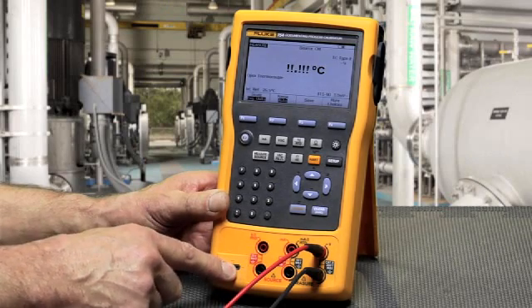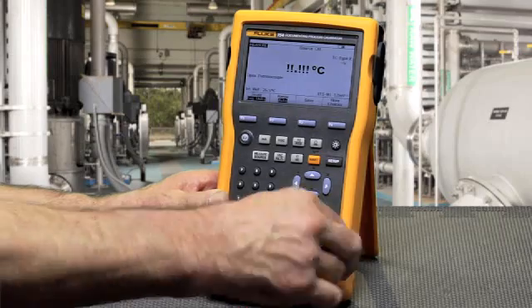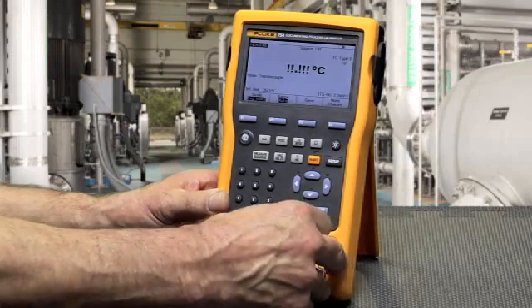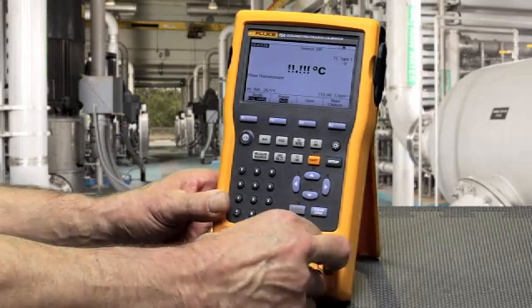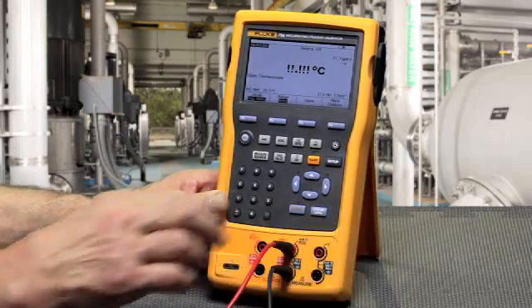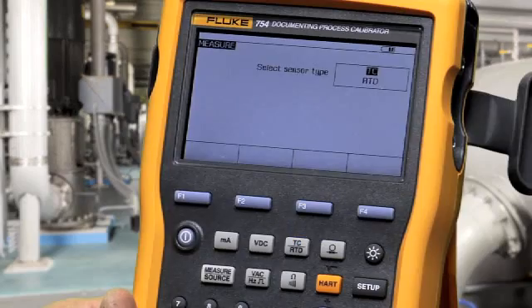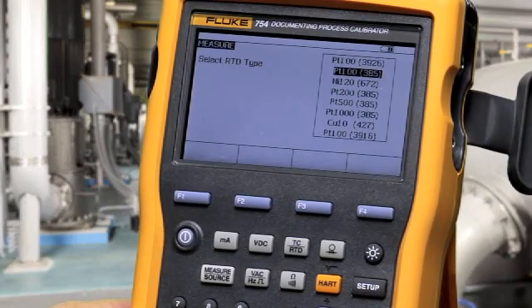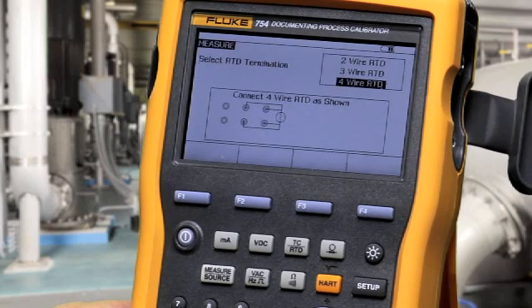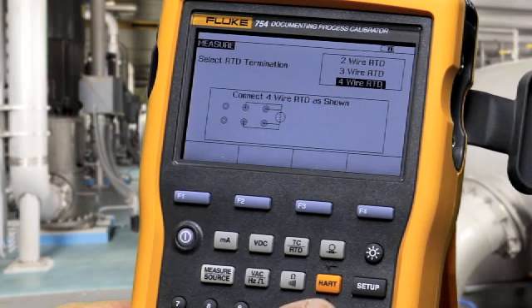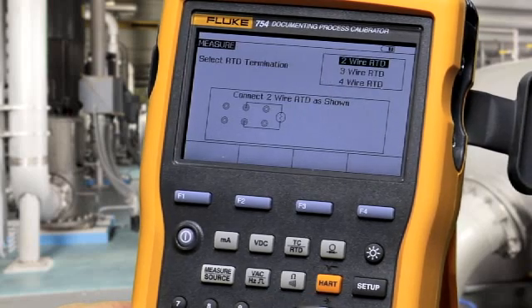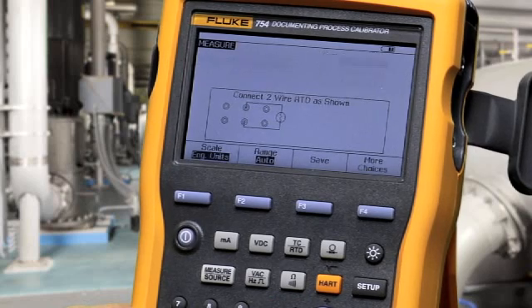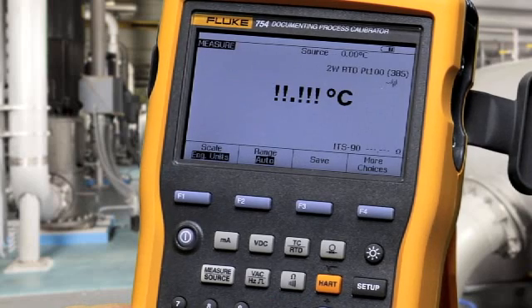To measure an RTD, make your connection on the RTD measurement jacks. Move the cursor to RTD and press enter. Select the RTD type, then select two, three, or four wire connection diagrams according to your sensor, and press enter to make the selection.